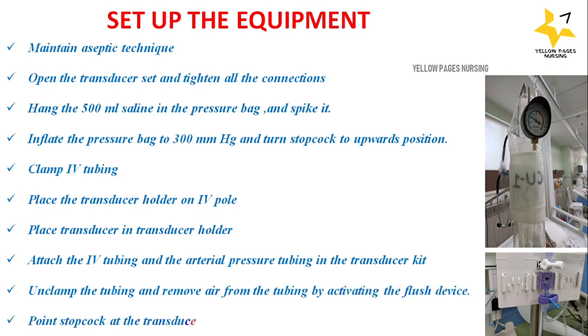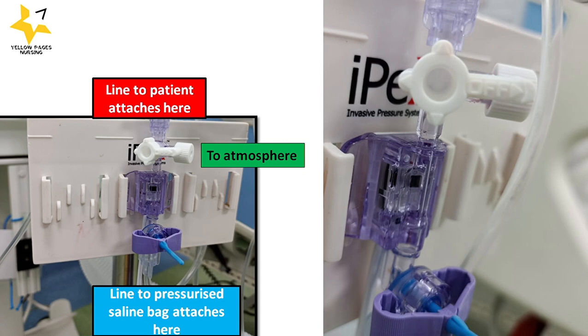Clamp the IV tubing, place the transducer holder on the IV pole, and place the transducer in the transducer holder. Attach the IV tubing and the arterial pressure tubing from the transducer kit. Unclamp the tubing and remove air by activating the flush device. Point the stopcock at the transducer horizontal and clamp the tube wings. The upper part of the setup connects to the arterial line of the patient and the lower part connects to the pressurized saline bag.